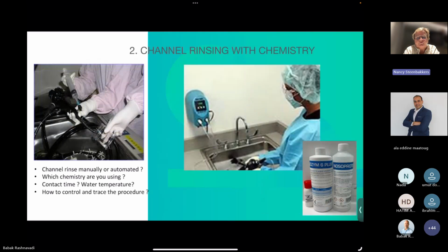And of course, you have to perform the channel rinsing with chemistry. So you have to respect the water temperature, because your detergent needs a specific water temperature. And you have to respect the contact time of your detergent. If you don't respect those two important steps, your endoscope is never getting rid of the biofilm. So this is the most important thing that you have to understand. Control your water temperature, put your detergent in it, and respect the contact time of your detergent. Otherwise, cleaning is not happening. That's clear as that. Next, please.